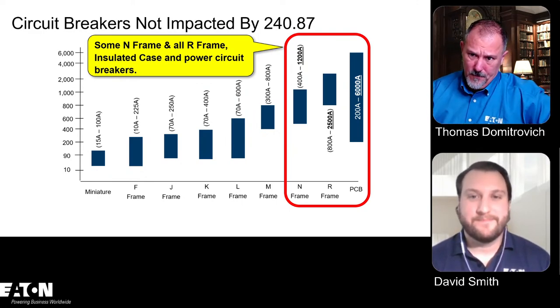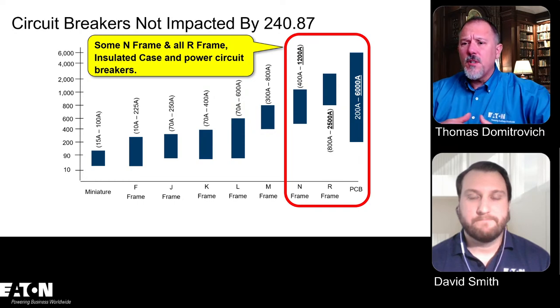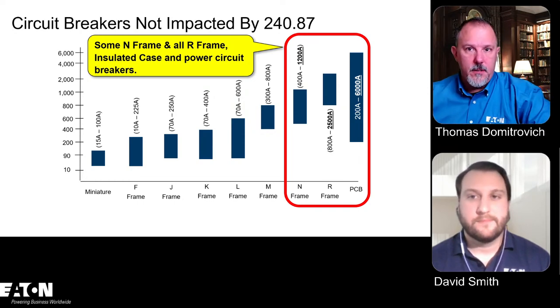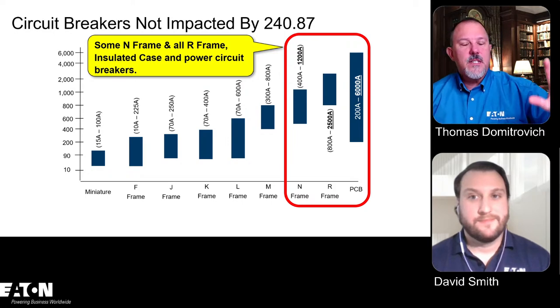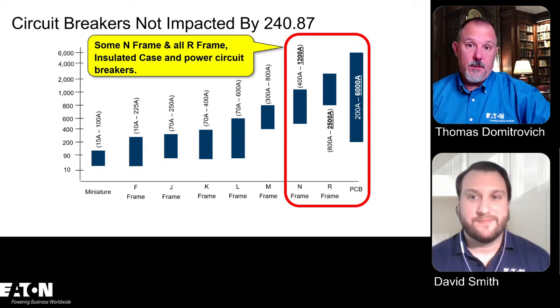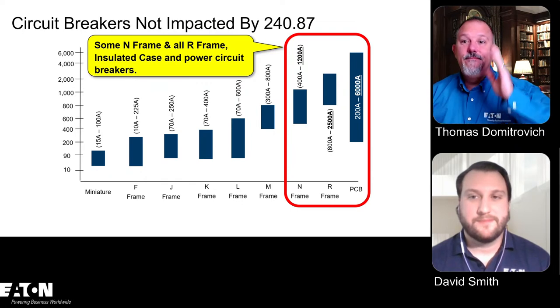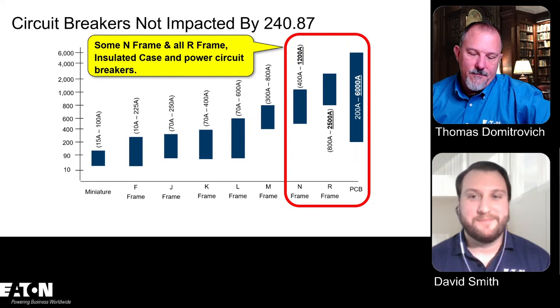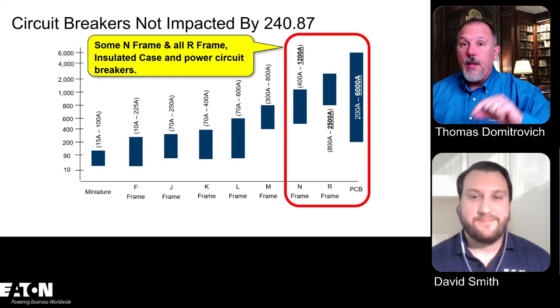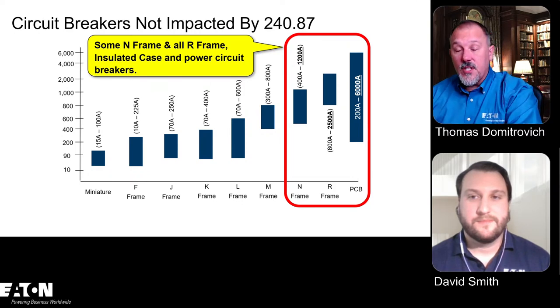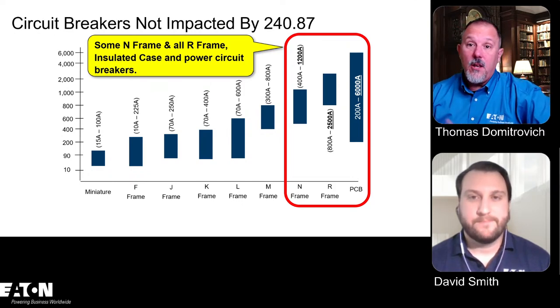Right. So they said, look, it's either going to be 1,200 or 800 or 2,500. There were some people at the table that wanted to take it to 2,500. The IBEW and some of the contractors said, no, we want to take it to 800. And they argued. And you know what got two thirds? 1,200 amps. There it is. Right. So now here we are in the 2023 code cycle, and Panel 10 is now saying, look, remember that discussion? We're going to take it down to 800 amps.